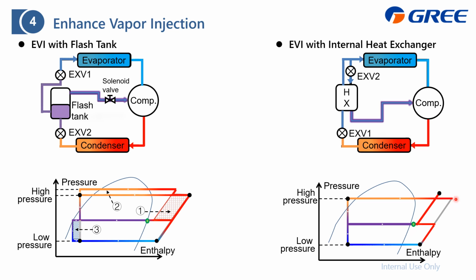And the first benefit is we can also lower the compressor discharge. And the second is also to raise the high pressure. And the third is you can also find that this refrigerant, after getting metered, will become low pressure and temperature, and then this amount can absorb heat from this main row in this internal heat exchanger. It can make itself completely vapor, which is going out from this curve.